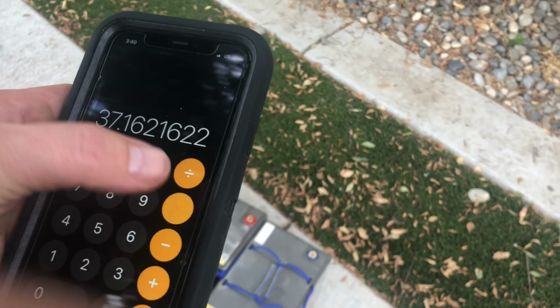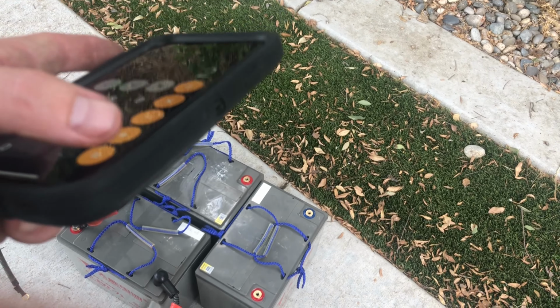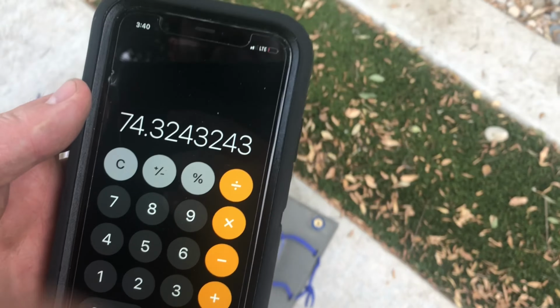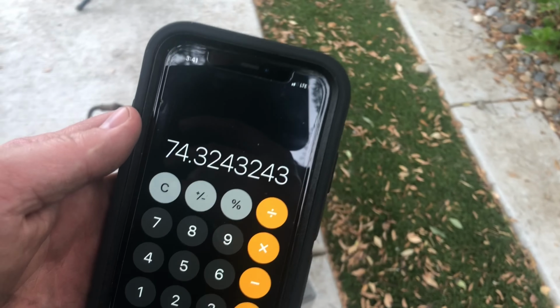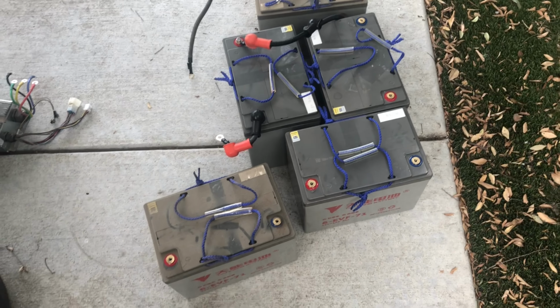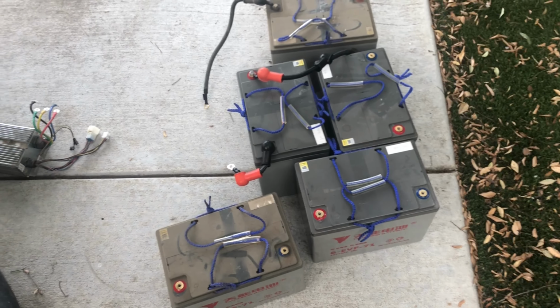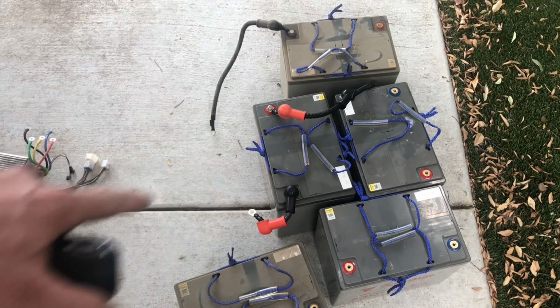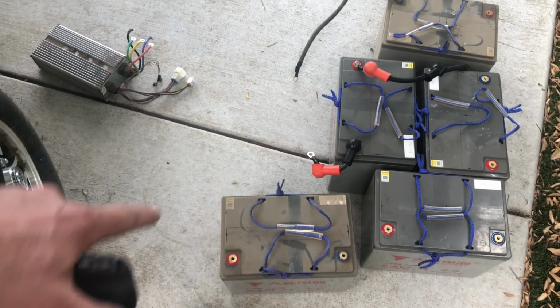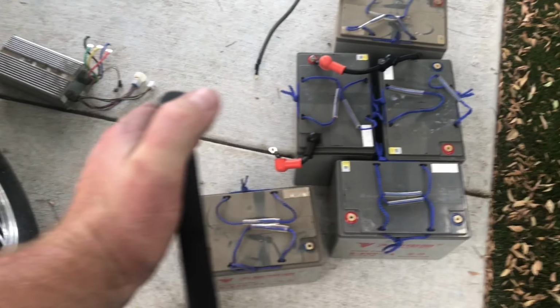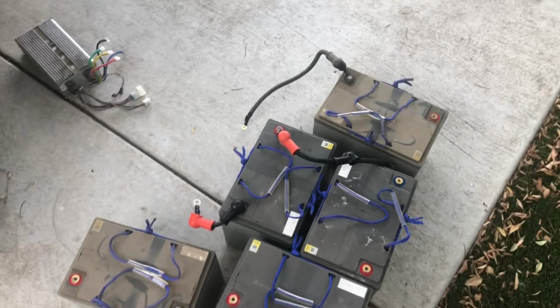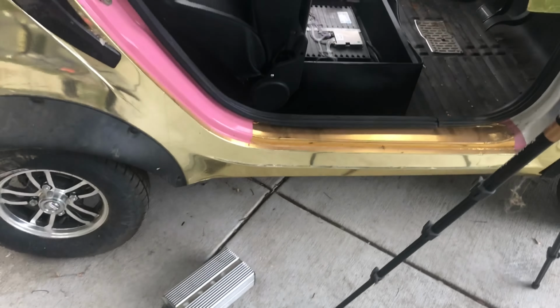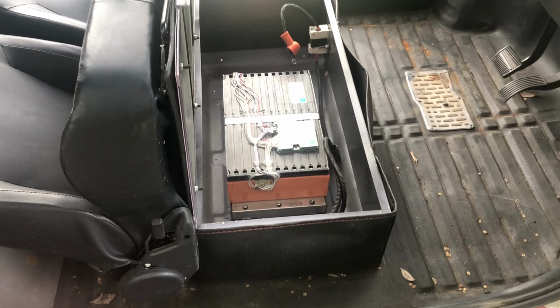37 amp hours is actually comparable to about a 74 amp hour lead acid, because of the discharge curve being so inefficient on a lead acid. These are rated at 71 amp hours over their whole usable range, but that range is basically just a linear decline in voltage for lead acid, whereas this is more of a flat decline which then tapers off at the end. So that's a whole bunch more usable voltage compared to a discharge curve that's completely linear. Functionally, it's not a downgrade in terms of amp hour rating.